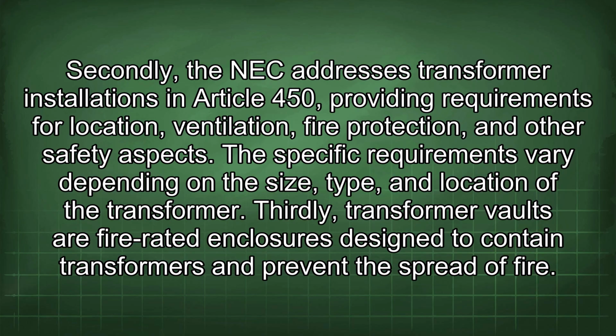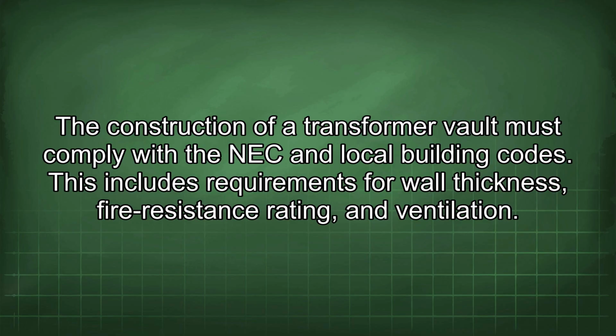Secondly, the NEC addresses transformer installations in Article 450, providing requirements for location, ventilation, fire protection, and other safety aspects. The specific requirements vary depending on the size, type, and location of the transformer. Thirdly, transformer vaults are fire-rated enclosures designed to contain transformers and prevent the spread of fire. The construction of a transformer vault must comply with the NEC and local building codes. This includes requirements for wall thickness, fire resistance rating, and ventilation.